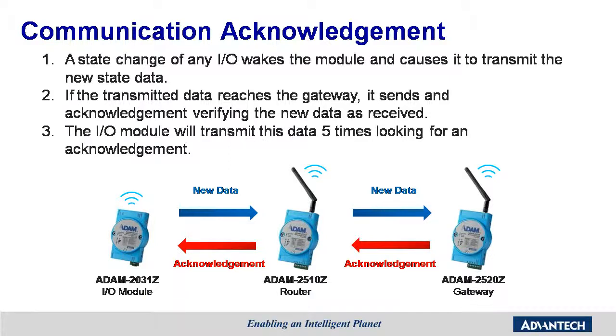When a sensor, transducer in our case, with built-in temperature and humidity sensing such as the 2131Z, senses some change of state or some change in the actual temperature or humidity, that input state is changed, and it automatically wakes up its transmitter and sends this new data to the gateway. In many applications, in our Advantech 2000 series, we also apply routers, which are a sort of repeater for the I/O modules to extend their range and allow them to continue to jump in a repeated fashion. So from one repeater to the next, we can go up to 1,000 meters or 1 kilometer, and that can be extended another 1,000 meters to the gateway module itself.